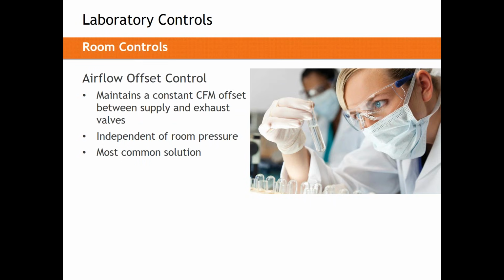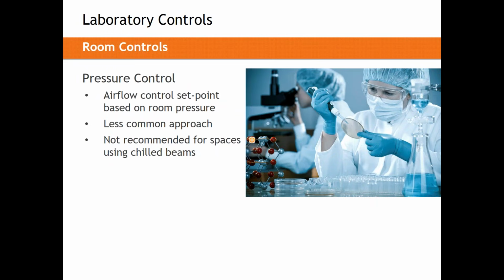Anytime you're doing high-speed control, so really anytime you're in a laboratory environment, this is the method of control you should be using. It's also very, very good in compounding pharmacies and operating rooms. The last thing I'm going to present, however, is pressure control. Pressure control is essentially identical. It uses a difference between supply and exhaust. However, instead of controlling to a CFM offset, it will control directly to a pressure.